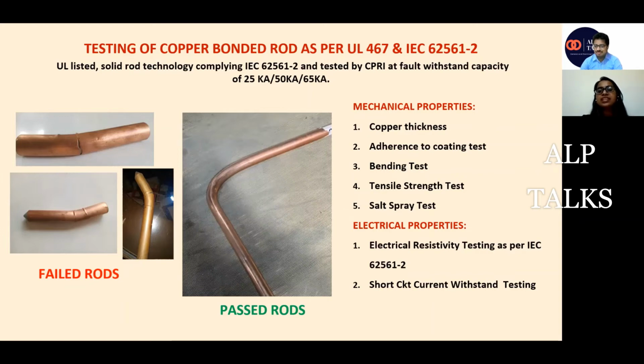Tensile strength is also tested. And the last one is the salt spray test to check the corrosion resistant property of these rods, so that we can bury them in any type of soil and they will not corrode when we install them in the soil. The corrosion resistance salt spray test is done as per UL 467 and IEC 62561 part 2.